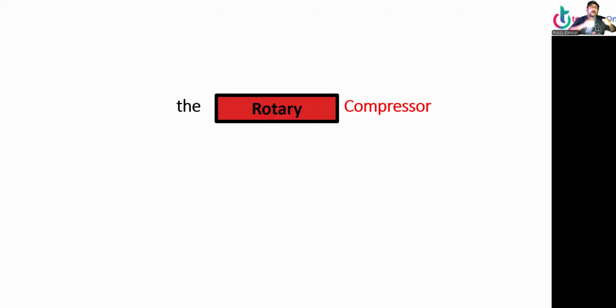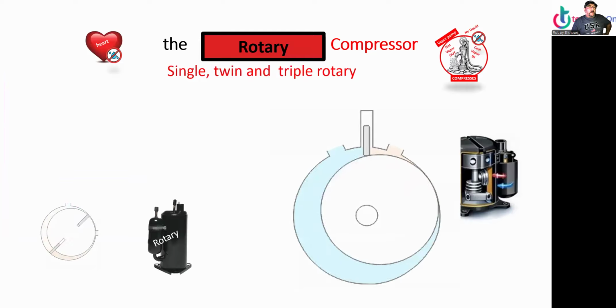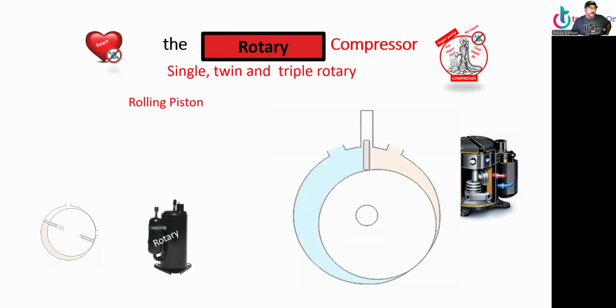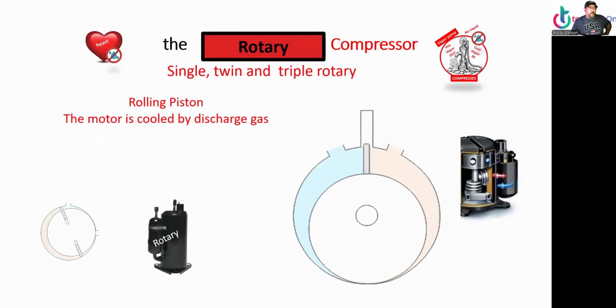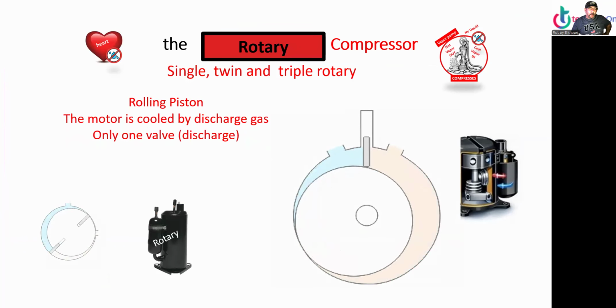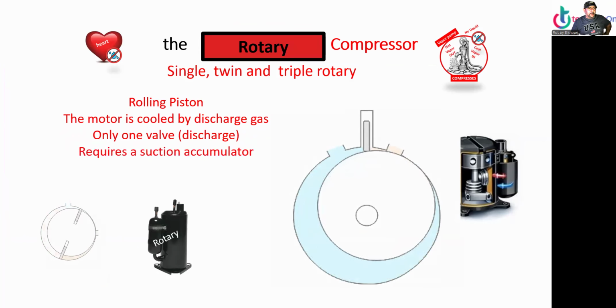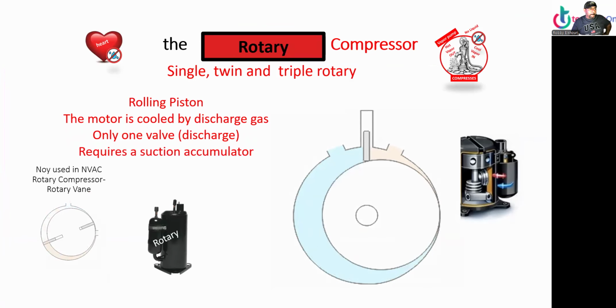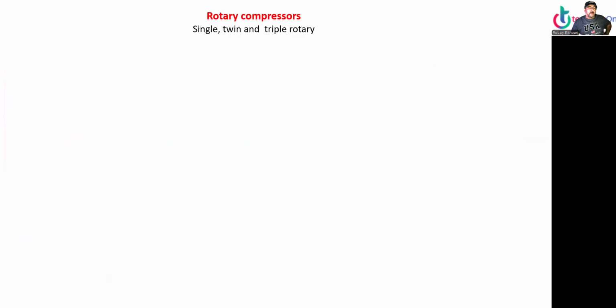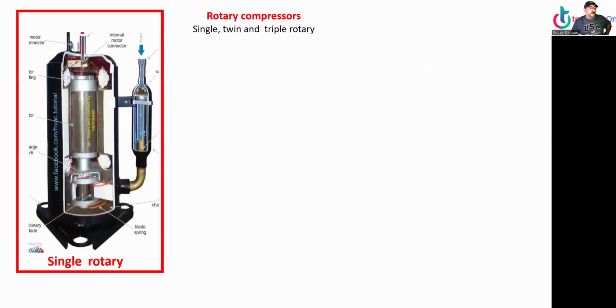The rotary compressor. So we have single, twin, and triple rotary. Rolling piston, the motor is cooled by the discharge gas. It's the only one where the motor is cooled by the discharge. Only one valve, the discharge valve, and it requires a suction accumulator. The rotary vane is not used in HVAC.